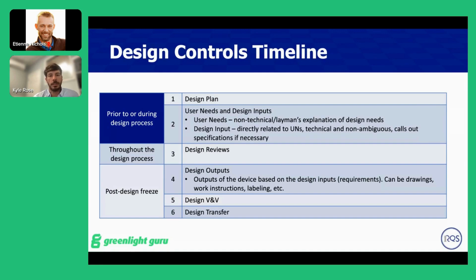As you begin to iterate on the device and work in this R&D phase, this is when you need to start identifying some user needs and design inputs. User needs are the high-level, non-technical explanation of the design needs and tie specifically to what the user is looking for from your device. And then design inputs relate directly to your user needs, but are more technical and call out specifications or things that can be tested against. So as you're starting to develop your device and moving from the R&D phase into more of a prototype manufacturing and testing phase, this is really when you need to dive in to make sure you have your user needs, you have your design plan, and you have your design inputs.